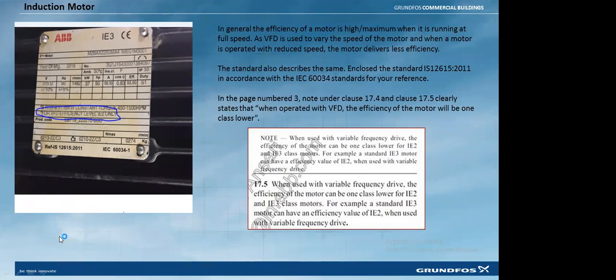But when that same pump is run with an external VFD, there is a possibility that when the pump is running at a partial load, whether at 75% load or 50% load, there will be a drop in efficiency. That is what the standards are saying. In general, the efficiency of a motor is at its maximum when running at full speed. As a VFD varies the speed and the motor is operated at a reduced speed, the motor delivers lesser efficiency. So if you have an IE3 motor with an external drive, at partial load the pump may deliver only the equivalent of IE2 efficiency.